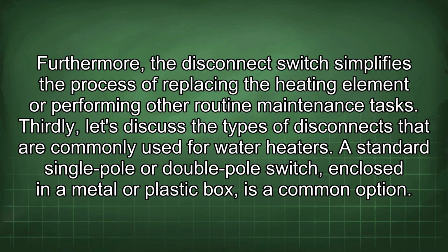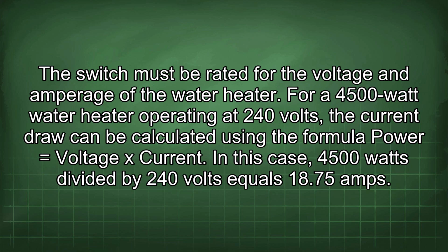Furthermore, the disconnect switch simplifies the process of replacing the heating element or performing other routine maintenance tasks. Thirdly, let's discuss the types of disconnects that are commonly used for water heaters. A standard single-pole or double-pole switch, enclosed in a metal or plastic box, is a common option. The switch must be rated for the voltage and amperage of the water heater.